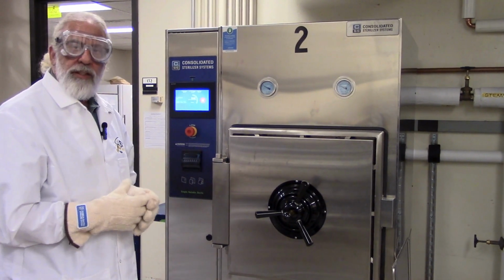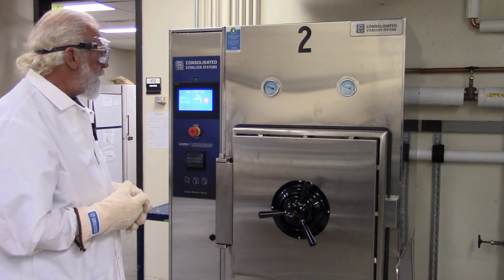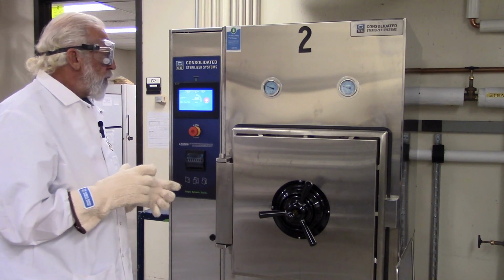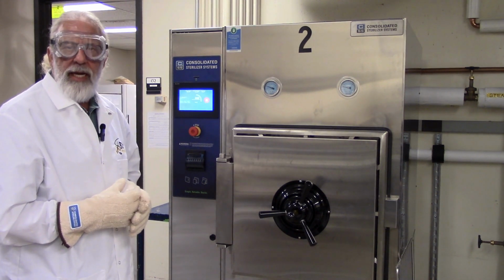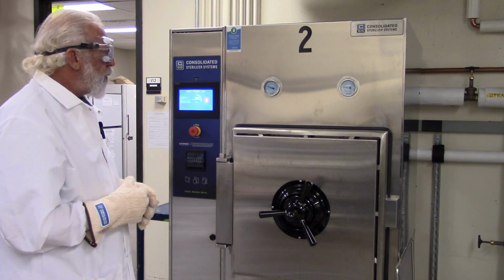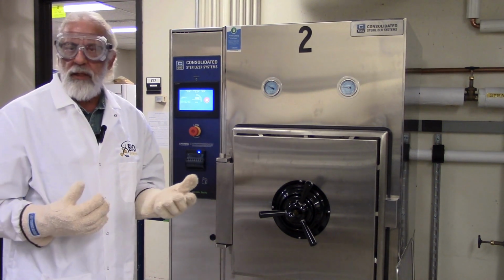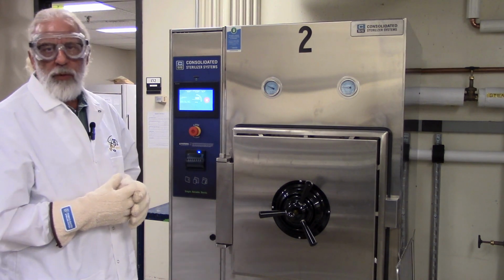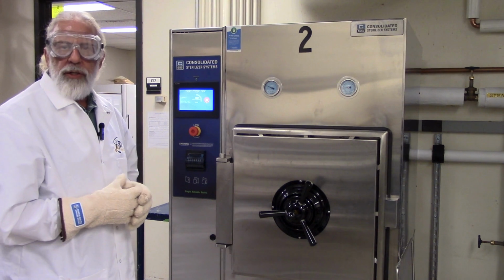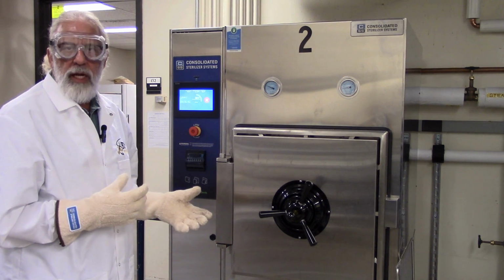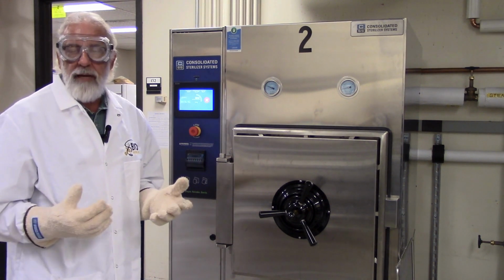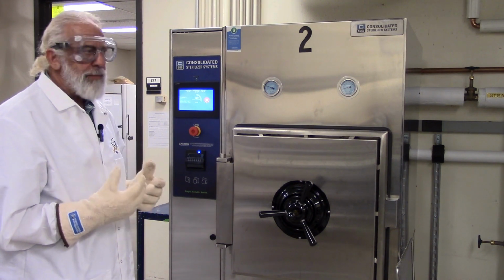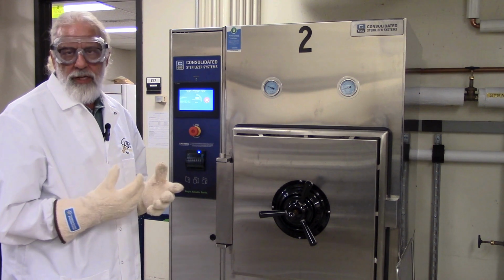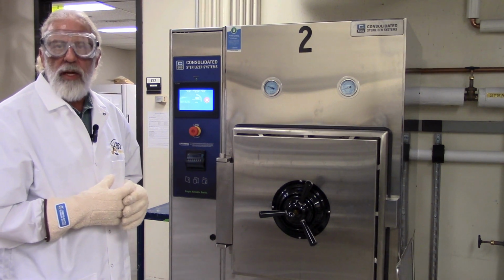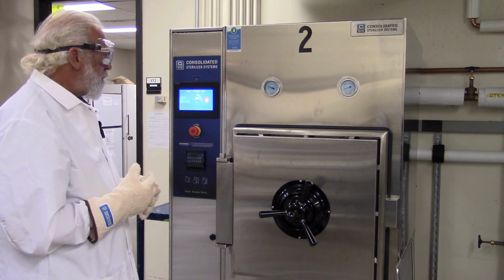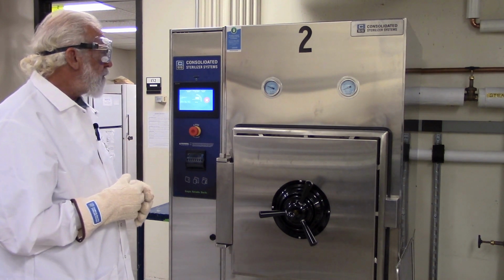So we finished the sterilization portion of the cycle, and it went for 15 minutes. It kicks into what they call a drying cycle at the end of the sterilization for a gravity load. If you were running a liquid load, it would say cooling rather than drying. The function of either cooling or drying is to remove the water and the condensation that will form on the outside of what you've autoclaved. The longer that time is set for, the more effective job it does. If you have a lot of issues with that, you can talk to us, and certain cycles can be modified and a special cycle can be designed as well. But it'll dry for probably most of the remaining time before it starts to exhaust.